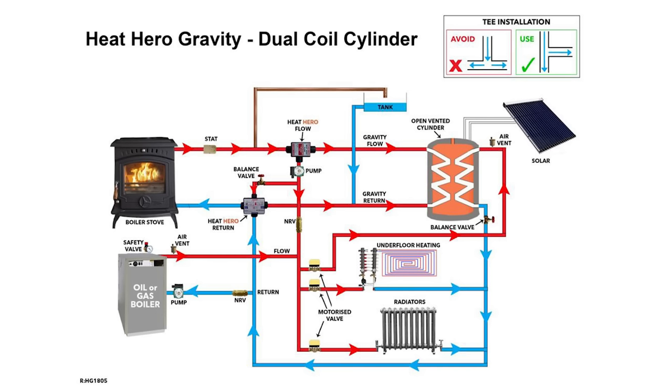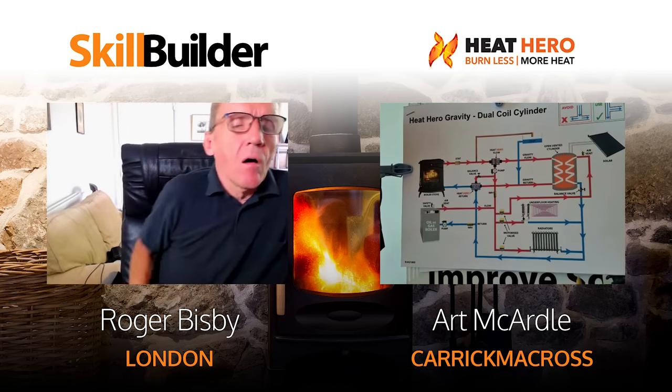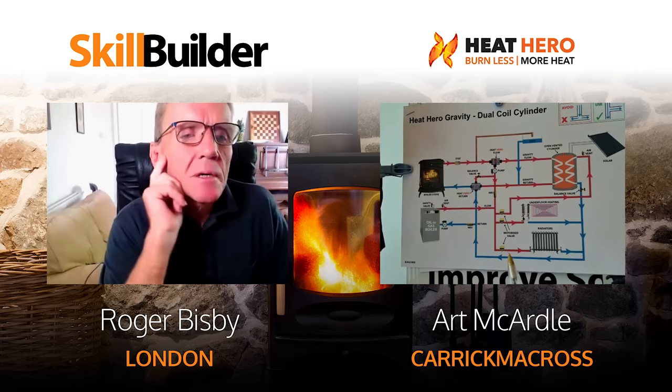When the pump stops it's back to gravity - these are full gravity systems. The water passes through without any air breakages, so you have a fully pumped system while retaining full gravity. You lay your stove as usual. The difference is you don't put your stat in the hot press anymore. Like an oil or gas boiler where the stat is built in because that's where the heat is - this is the same. When you lay your stove, the stat is put as close to the stove as possible on the flow, because that's where you monitor the heat.